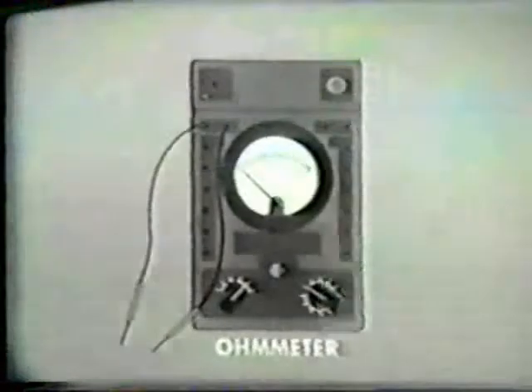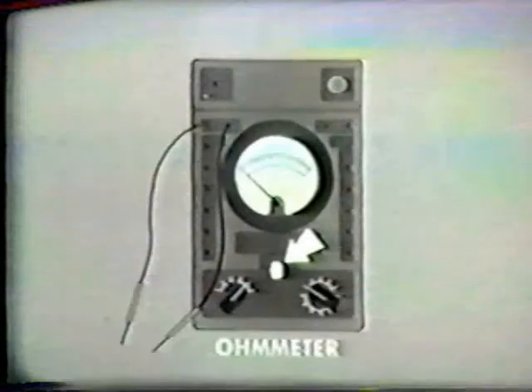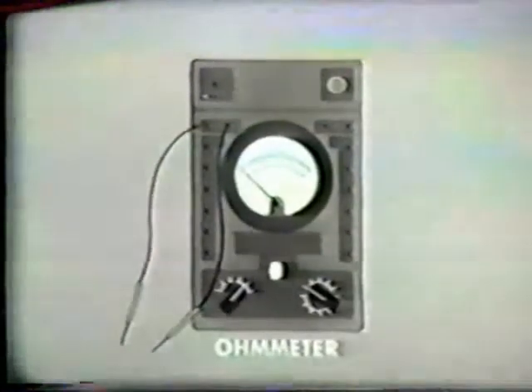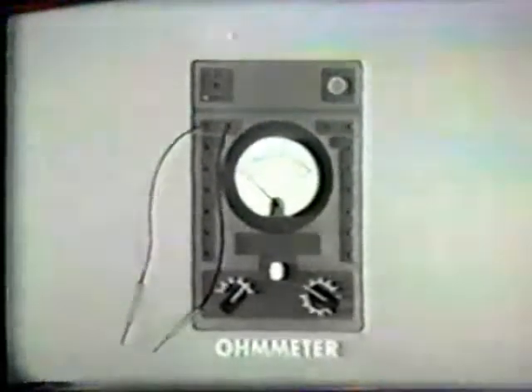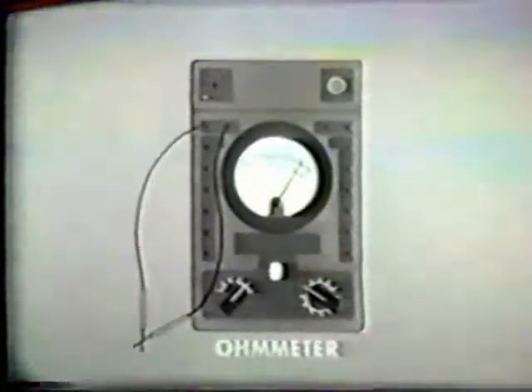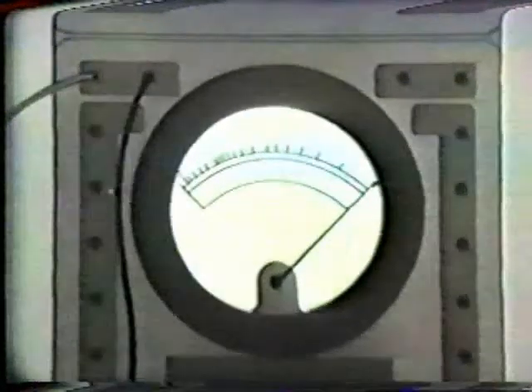All that remains to be done now is to use the ohms zero adjustment knob to zero the ohm meter needle. Connect the test leads together and check the scale. Rotate the ohms zero adjustment knob until the needle is at 0. It is necessary to zero the needle every time you use an ohm meter because ohm meter batteries deteriorate with use and age.